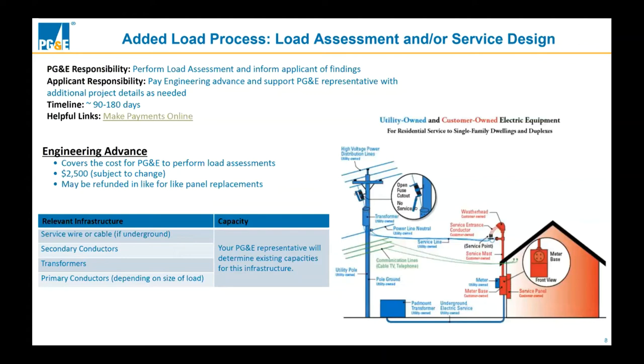So what exactly are we assessing when we talk about load assessments? The relevant infrastructure for these types of applications is the service wire or cable, if underground, the secondary conductor, the transformer, and, depending on the size of the building and the end uses being replaced, the primary conductors as well. If we need to go beyond just the primary conductors, we'll do that. The PG&E representative will assess the existing capacities of that infrastructure against the incremental load presented in the application, and ensure the facilities can accommodate the incremental load along with everything else it's serving.